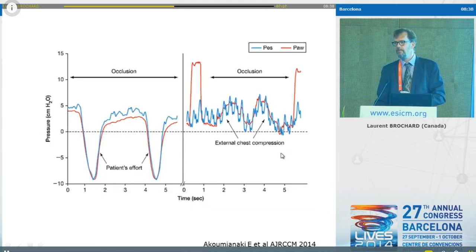It's not finished, because to be sure you have a reliable signal, you need to do what is called an occlusion test. What's an occlusion test? It's very simple. It's the comparison of the esophageal pressure signal and the airway pressure signal when you have no flow. This is an example when the patient is spontaneously breathing, and this is an example when the patient is passively insufflated. When he's spontaneously breathing, you occlude the airway with a pause on the ventilator, and the esophageal pressure negative swing should be very, very similar to the airway pressure negative swing.